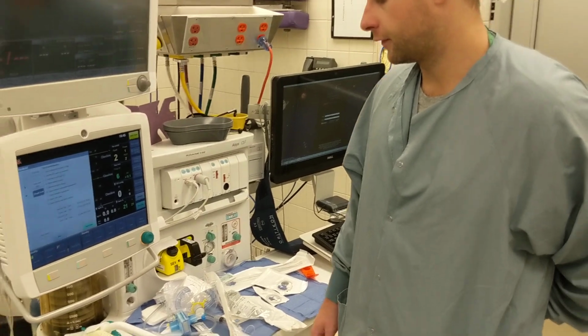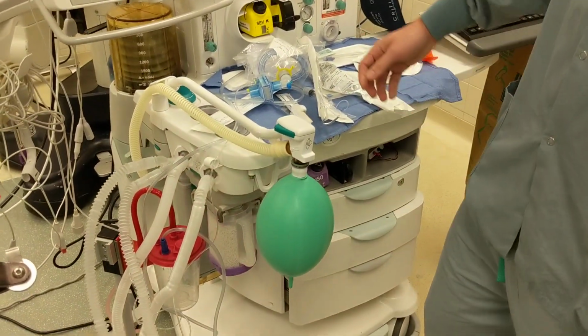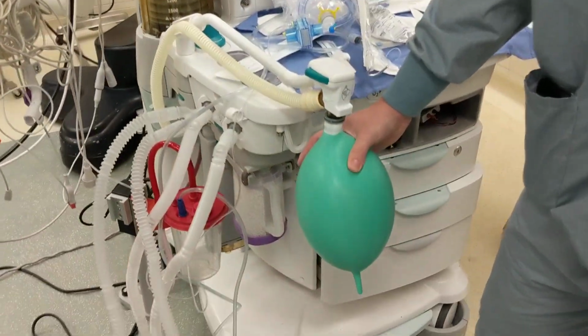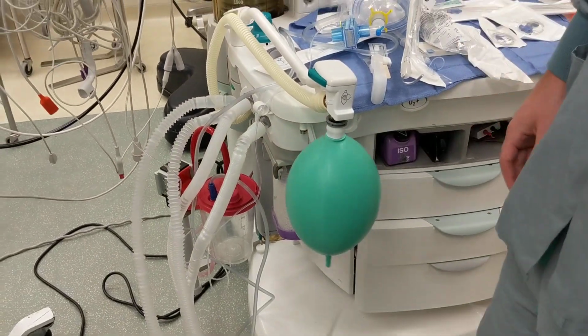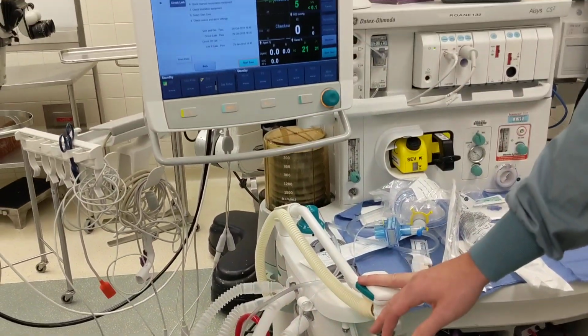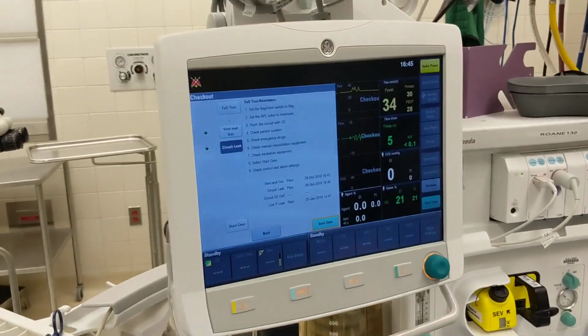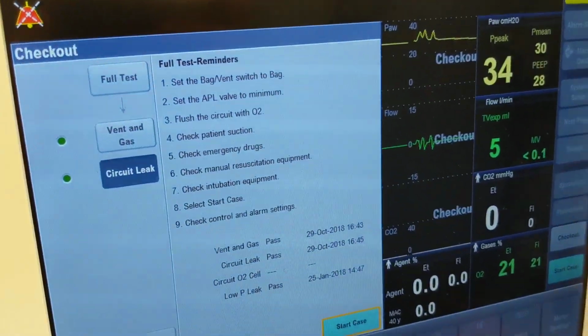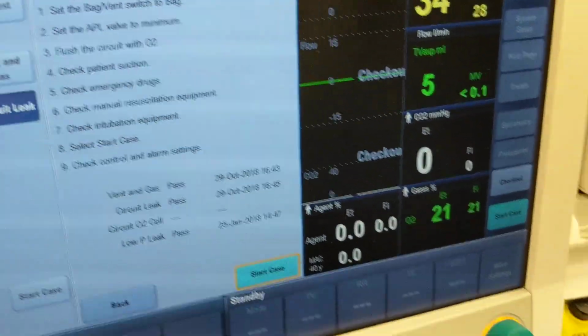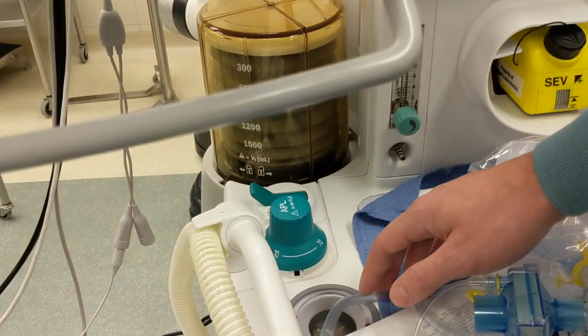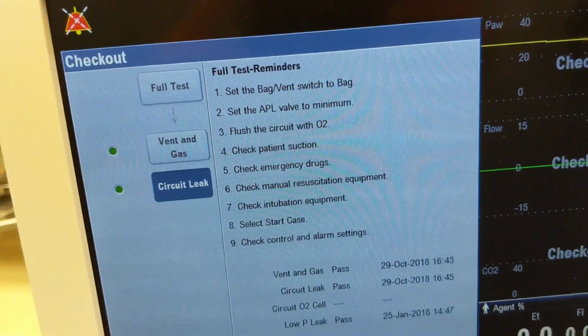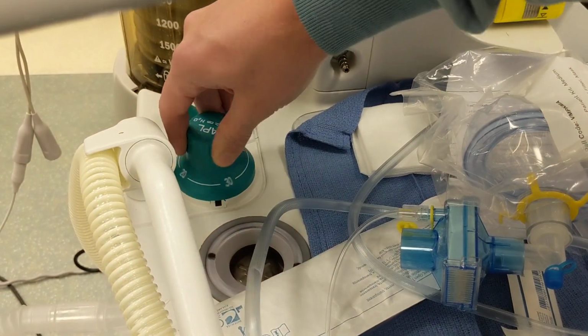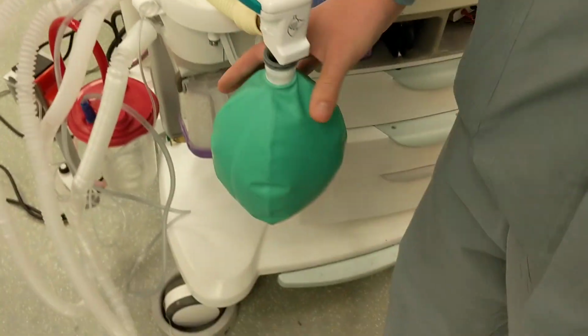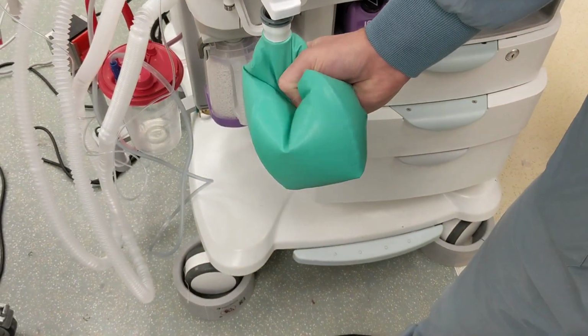Now that this step of the checkoff is done, we can see that the valve is closed. The bag is holding air. We know that there's no leak anywhere in the circuit. And we can go back to the full test reminders. Select the bag vent, switch to bag. We're currently on bag from the last step of the procedure. We're going to set the APL valve to minimum. We're going to switch back, open it up, and we can see how the bag lets up, and if we squeeze on it, it's not holding any pressure.